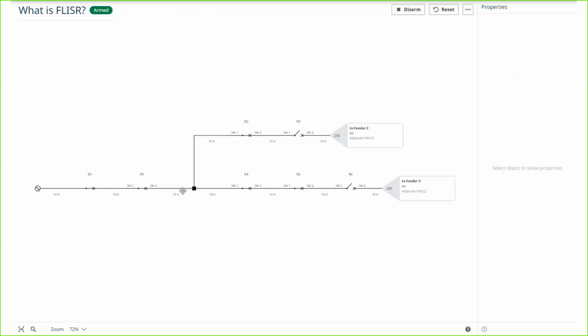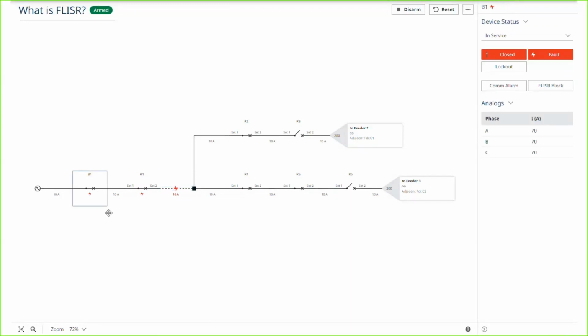So this is the same circuit. I'm going to place a fault in the exact same spot. You're going to see that recloser 1 and breaker 1 both see it. Now, if they are set correctly, they should coordinate. Recloser 1 will lock out. But what if they aren't? What if the breaker locks out?